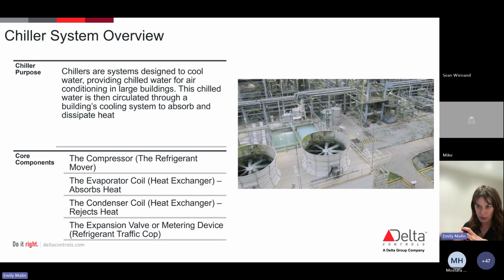That's what's actually going to compress the refrigerant and increase its temperature. Our evaporator is where the refrigerant is going to be absorbing that heat from the building's water system. Then it's going to go into our condenser coil, which is releasing that heat to the outside. And then our pump is going to circulate that water back through the entire system. And that's where our expansion valve and metering devices come into play. So essentially, all of these components are working together in a refrigeration cycle, which is going to effectively manage that heat transfer outside of the building.